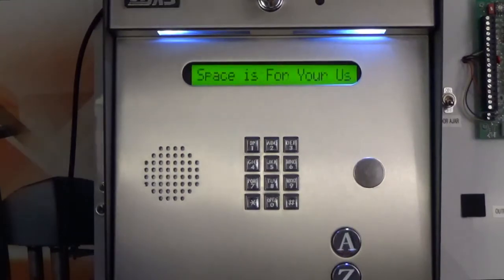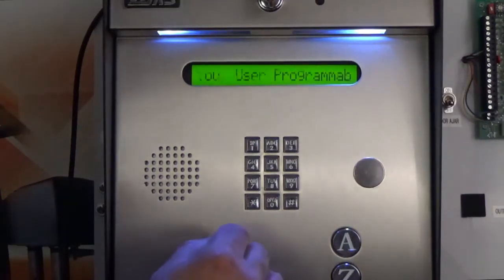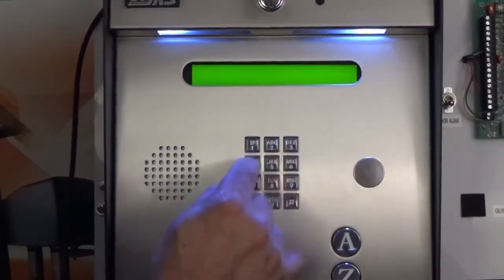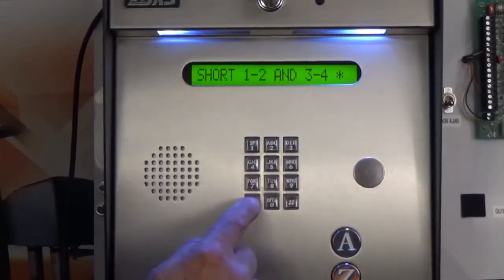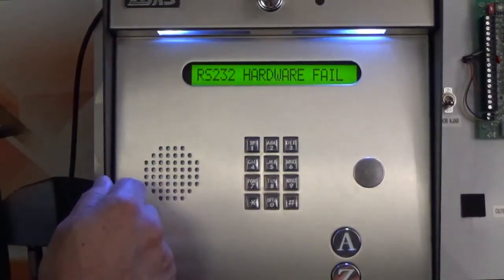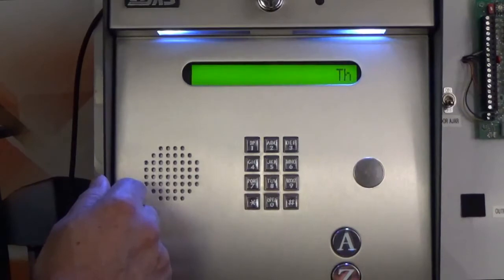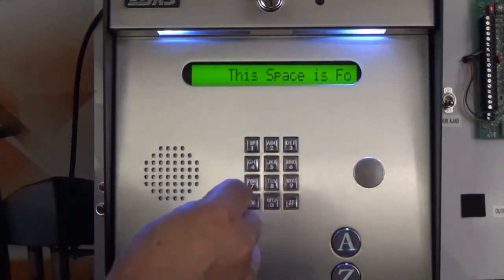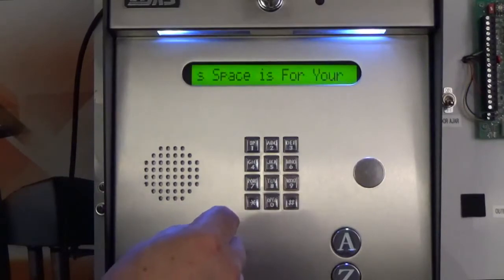Let's go ahead and simulate a failure now, and we'll start the test again. And we'll hit star again. Hardware fail was read on the display, and you notice it had multiple tones at the end of the test, indicating the test was a failure.